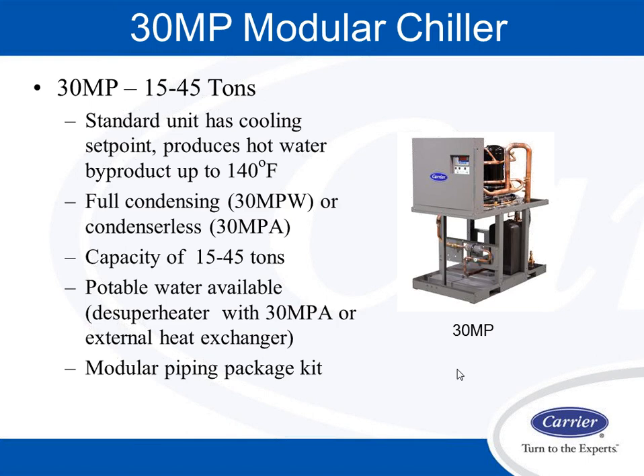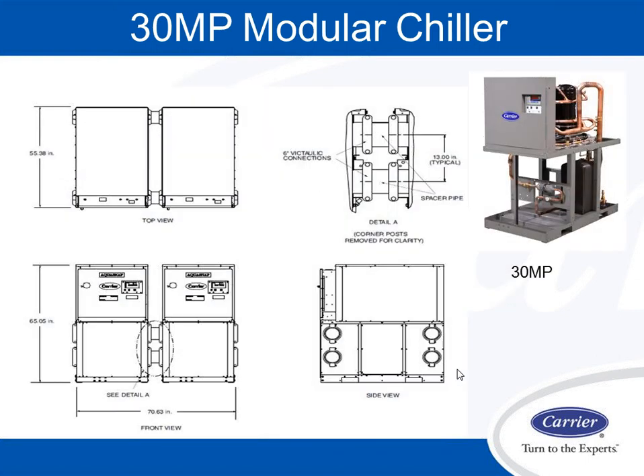But really, the most important thing I think is that we often compete with that multi-stack product in the modular chiller business, and now we have a modular piping package that goes along with this machine, which you can see on the next slide. So we come with this Victaulic piping connection kit, and we could pipe up to 8 of these machines in parallel to operate the chiller plant. So now I have 8 of these machines that I could modularly put in. They all fit in an elevator for replacement applications.